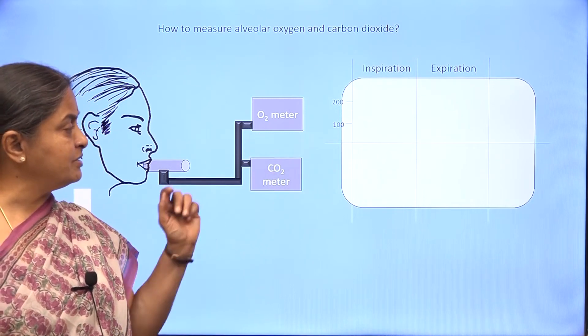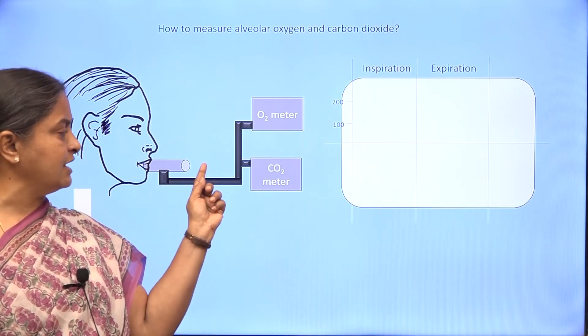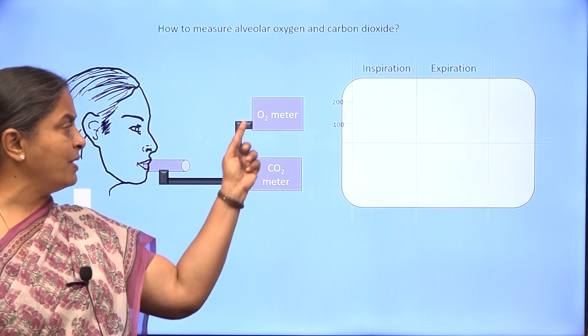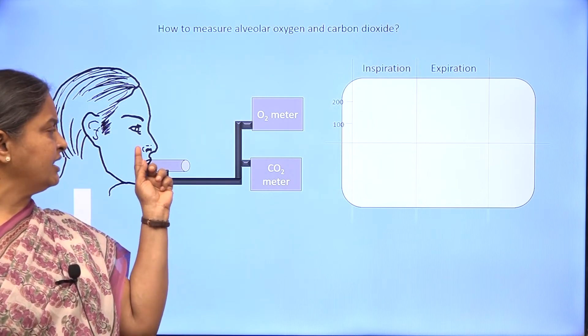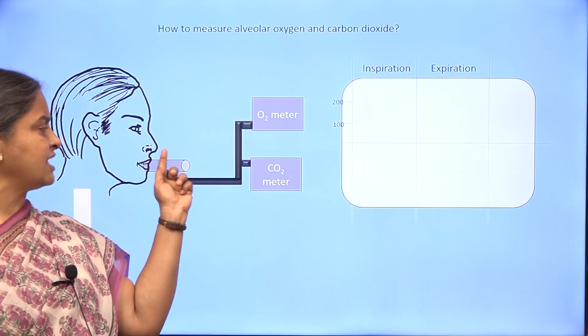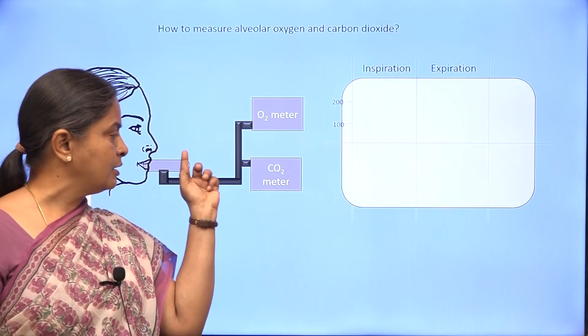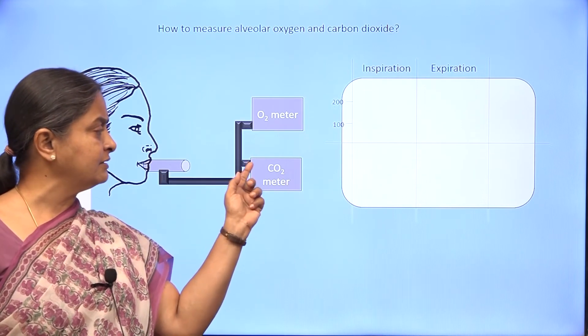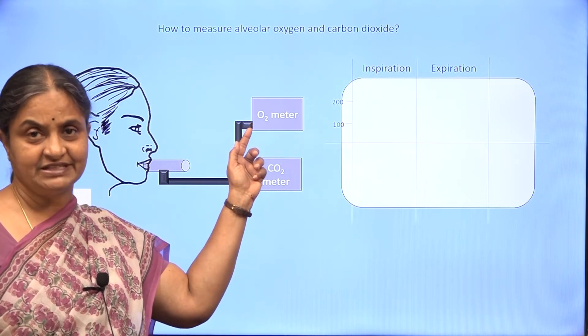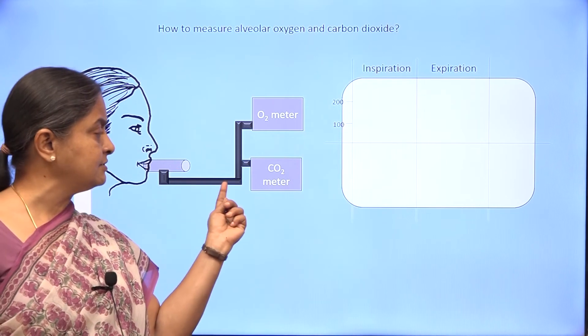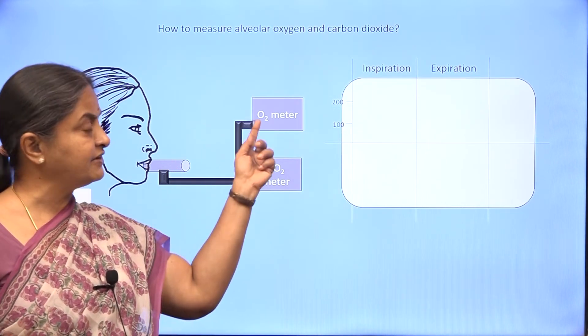These two meters get a sample of the air that you breathe in and breathe out through a pump. This does not have to be a tube in the mouth — you can breathe through your nose as you would normally. A small tubing placed at the outside of the nose will help deliver a certain percentage of the air that you inhale and exhale, say 10%. A small pump here sucks in 10% of the air that goes in and out and delivers it to the meters.